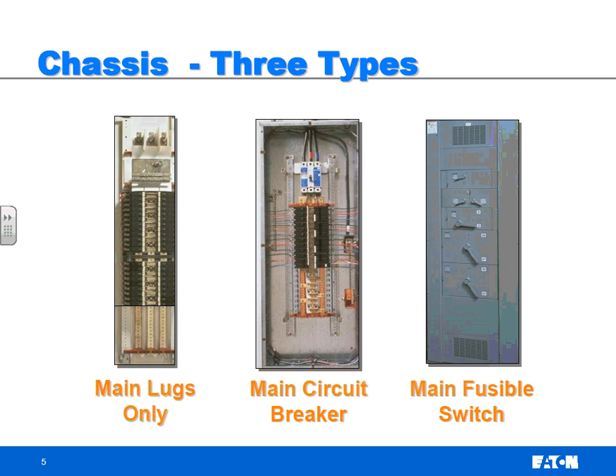It's going to have, they'll call it a thermomagnetic circuit breaker, and you're talking about the trip unit type. So this one's a little small. This one here is a 400 amp breaker. Okay, and right here is the trip unit itself. In these smaller ones, you don't have access to the trip unit. They're more cost effective. With the larger ones, you have more access.